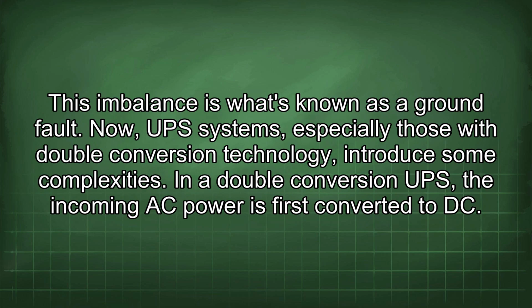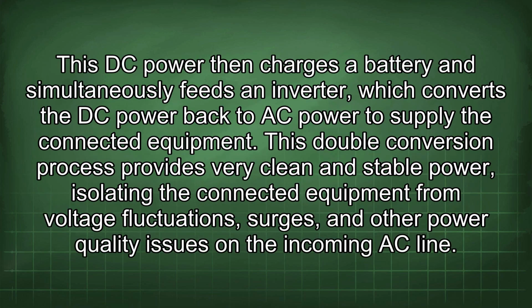Now, UPS systems, especially those with double conversion technology, introduce some complexities. In a double conversion UPS, the incoming AC power is first converted to DC. This DC power then charges a battery and simultaneously feeds an inverter, which converts the DC power back to AC power to supply the connected equipment. This double conversion process provides very clean and stable power, isolating the connected equipment from voltage fluctuations, surges, and other power quality issues on the incoming AC line.